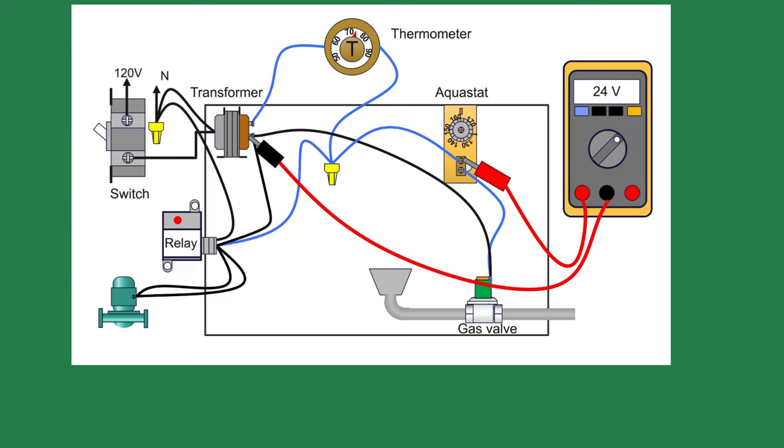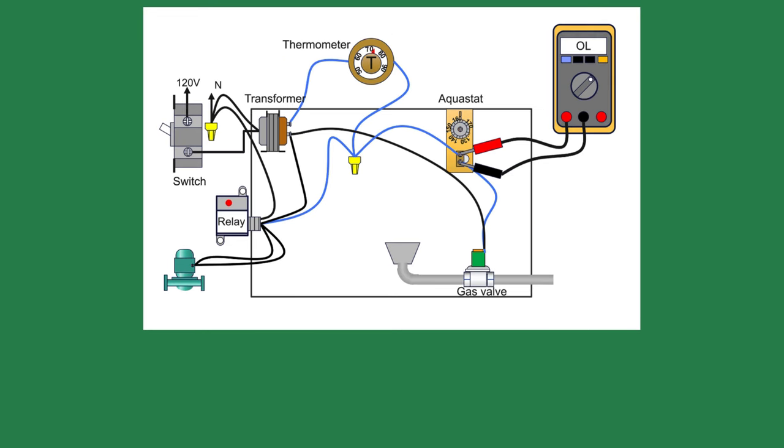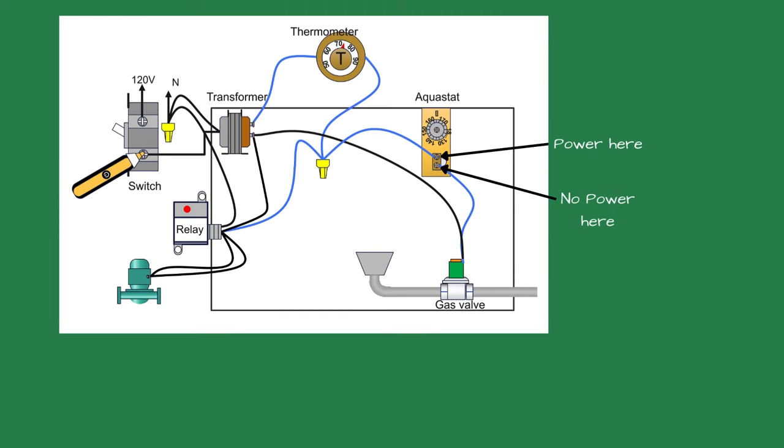The boiler circulator starts when the thermostat calls for heat. If we have power to both screws on the aquastat, we know the water temperature of the boiler is below the set point of the aquastat. Some techs will check the continuity across the two screws, but I have found this can give you a false reading of being made due to the wiring interference. If I have power on one side and none on the other, the water temperature is above the aquastat setting or the aquastat is defective.